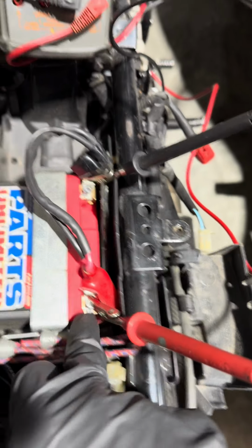A lot of the times it's going to be one of these two items. Again, you're going to want to check your wiring too, because it is possible that you have a loose connection inside of this plug. It could be rattling around if this plug's melted. A lot of the times if the plug is already melted, it's already past the point of just that being the issue. Most of the time one of these two components will have failed, but I have in a few rare cases seen where it was just faulty wiring or a faulty plug. But we will start with the easier thing to test here, which is going to be the stator.